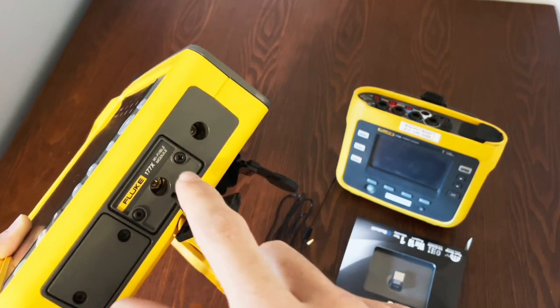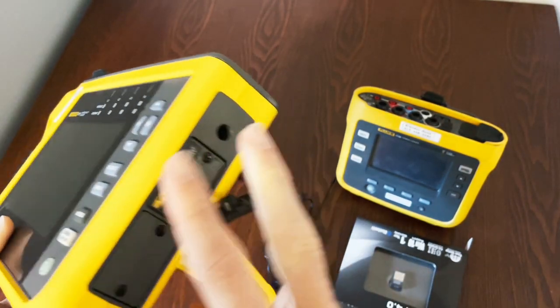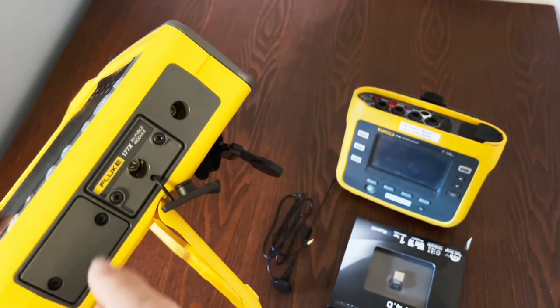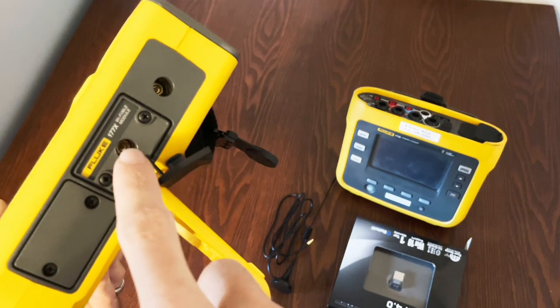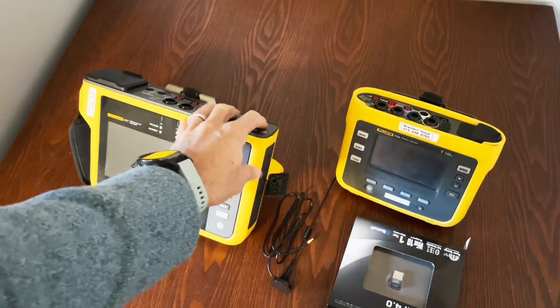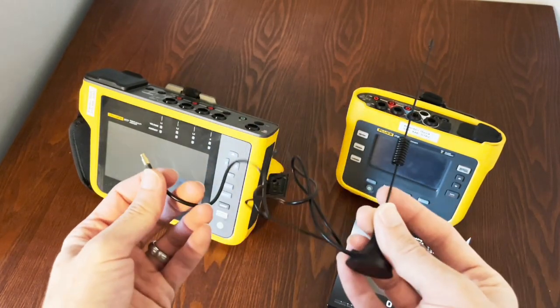On Wi-Fi, you can connect across the plant, log in just like with the cell card, use VNC to control it, or download data with Fluke Energy Analyze. The Bluetooth capability allows you to connect Fluke Connect tools to this device — up to two of them — so you can correlate additional readings like temperature or a 4–20 mA output. However, the 1777 does not come with an antenna included.